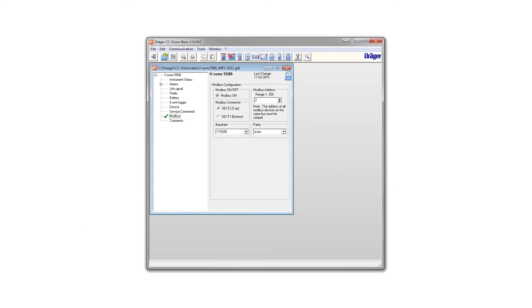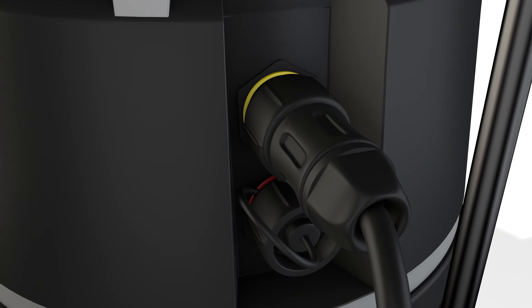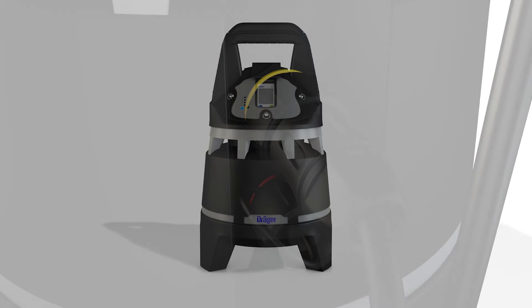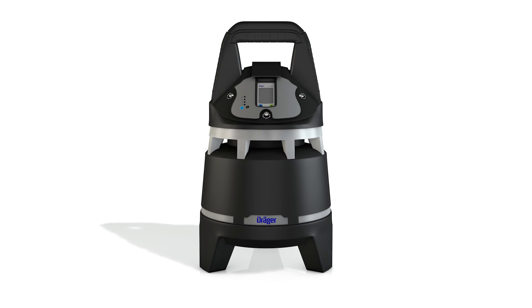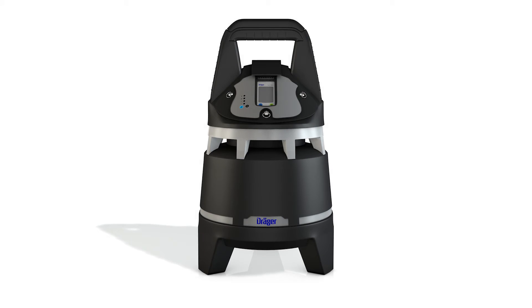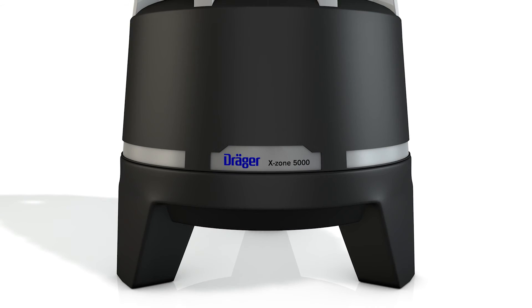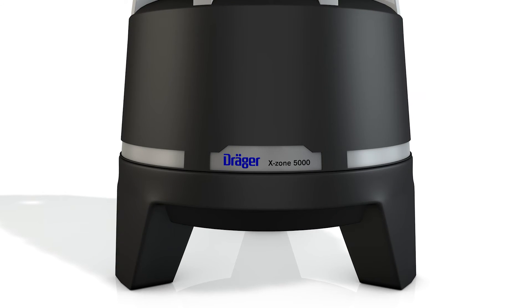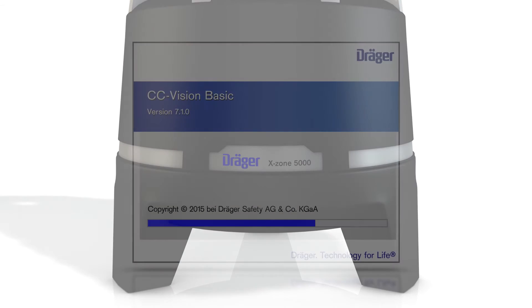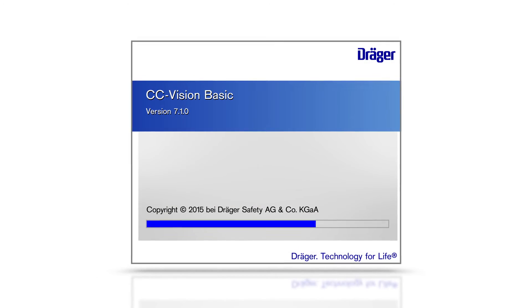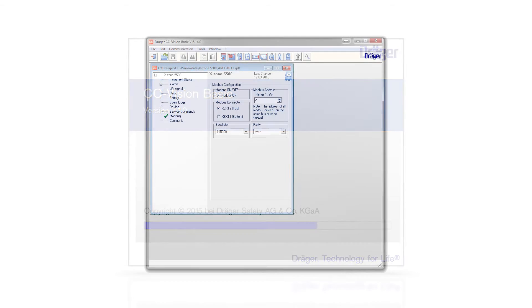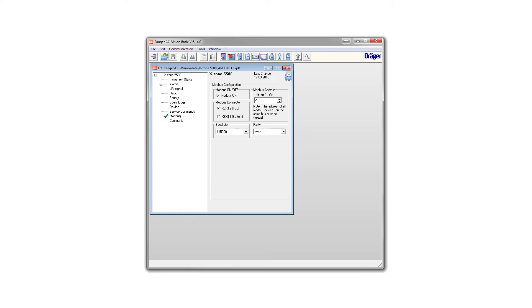Make sure that the modbus function on the X-Zone is on and that the signal on the upper connector is on. That is the default setting for the X-Zone 5500. The X-Zone 5000 must be activated by Draeger service. You can check the configuration of the X-Zone with the CC Vision software.